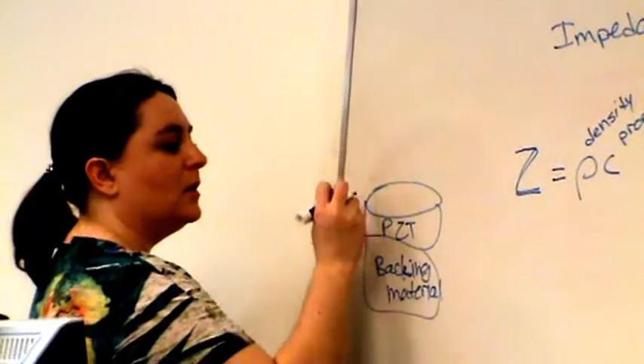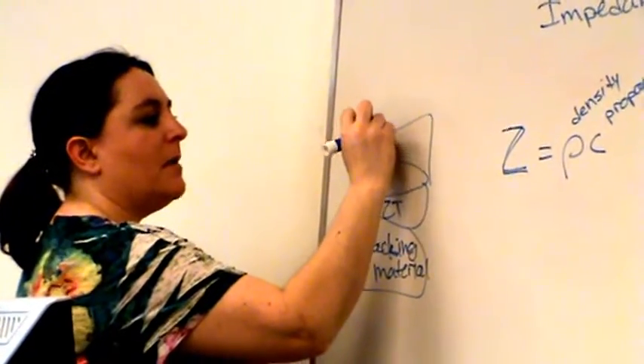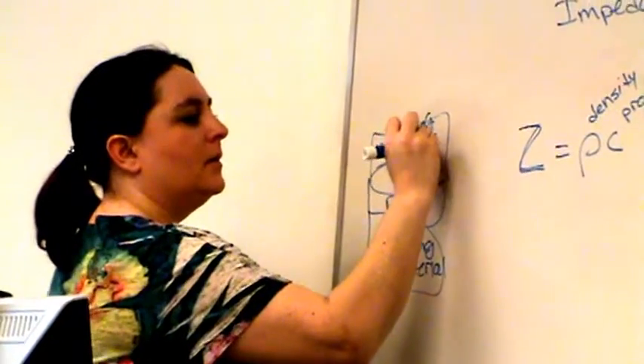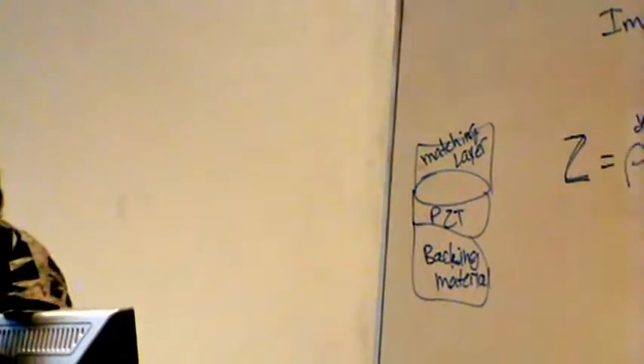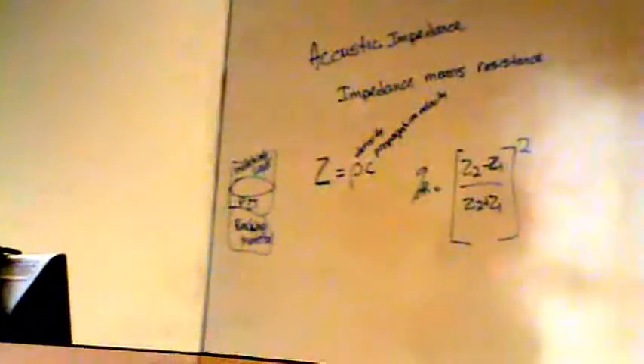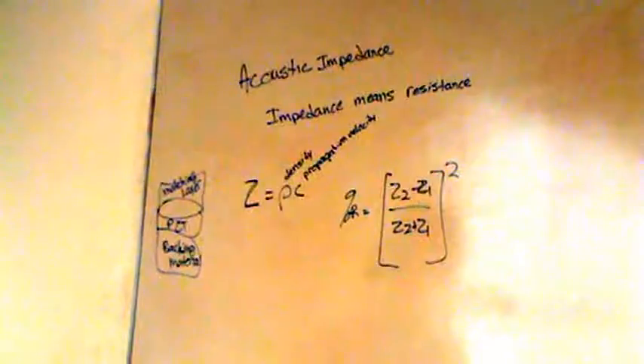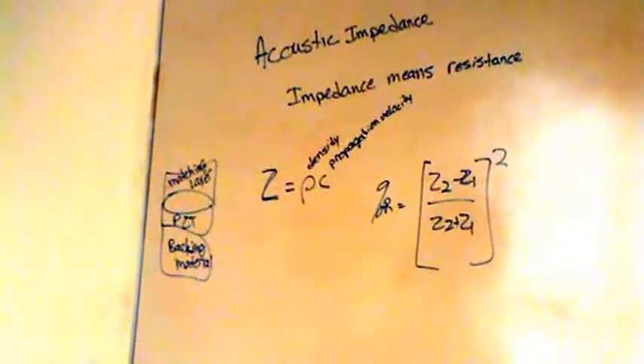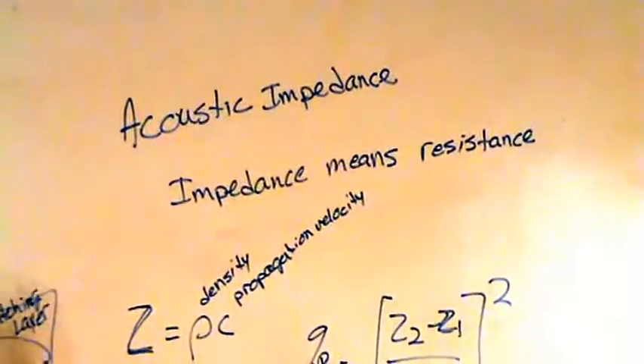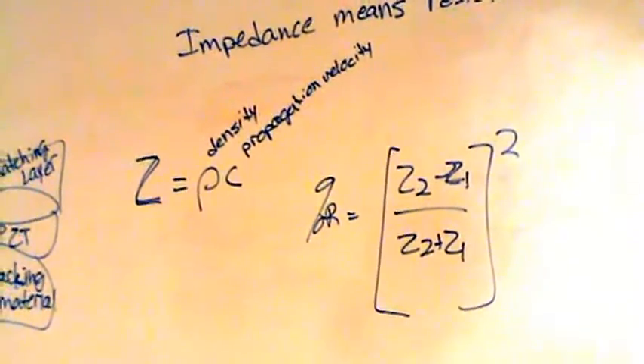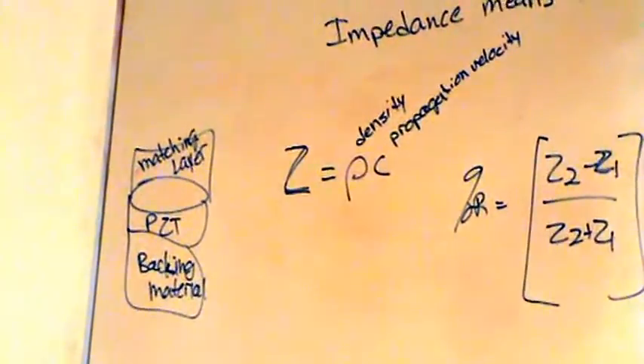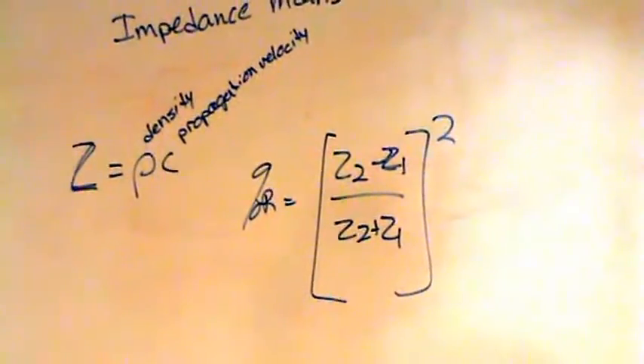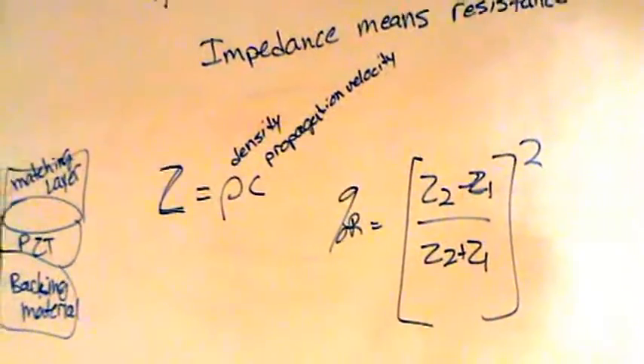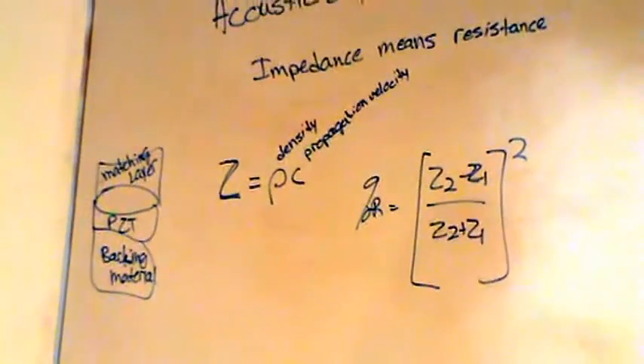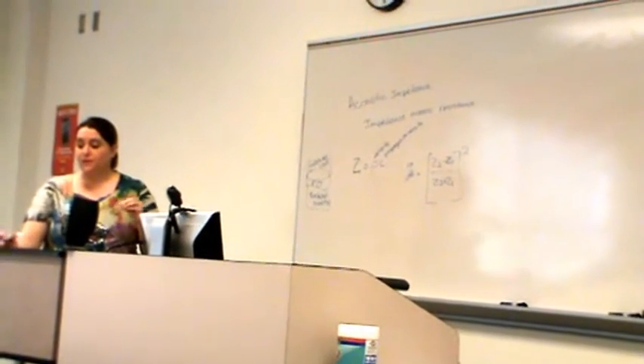And then we have that other layer up here. Right, this was the matching layer. What was the whole purpose of the matching layer? Right, it's to lessen the acoustic impedance mismatch between the crystal and soft tissue. So that's also the reason why we use gel. The acoustic impedance mismatch between even a matching layer and air is very, very high. So we would have a lot of reflection if we had an air layer in between the matching layer and the skin. So we put that gel in there that also lessens that acoustic impedance mismatch. So not only do we have to be worried about it in relation to reflections in the body, but even the way the transducer works, we have to have that thing that reduces that acoustic impedance mismatch.